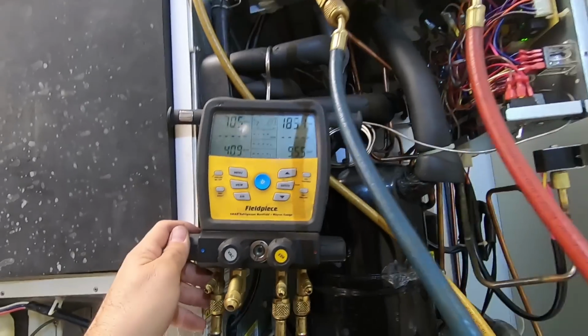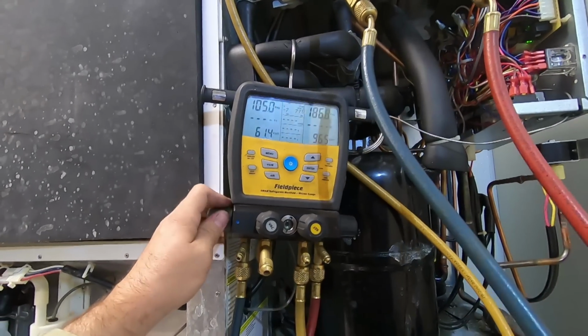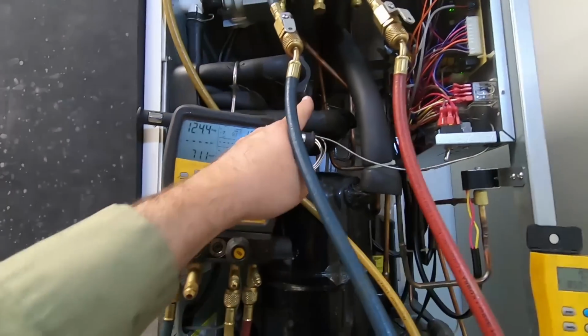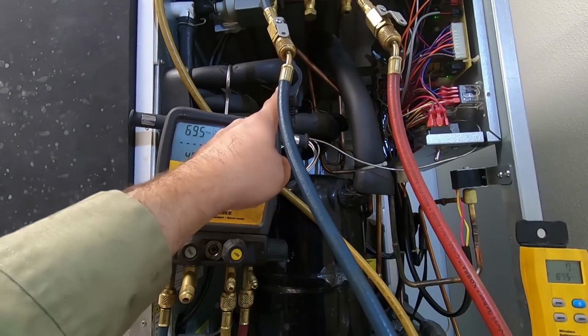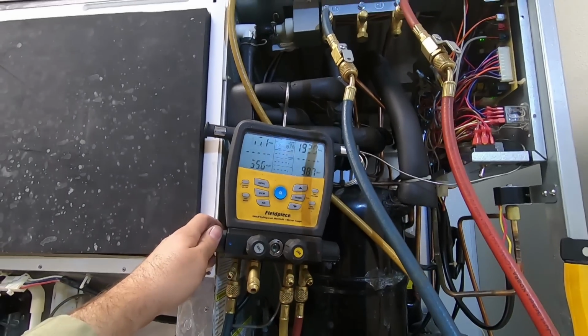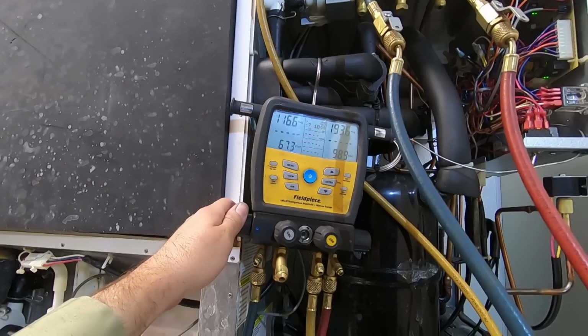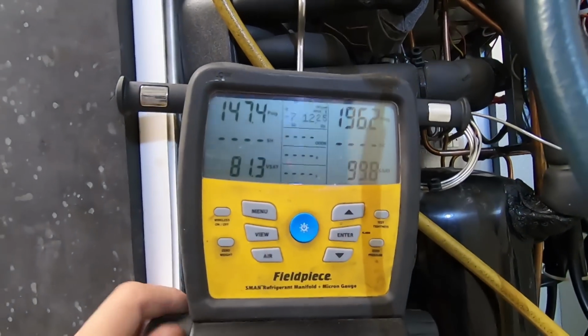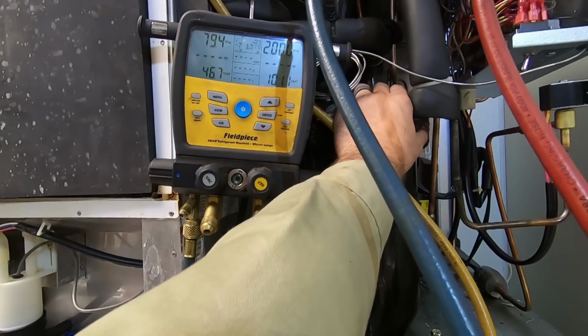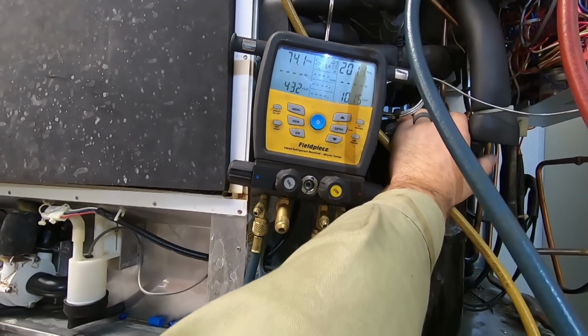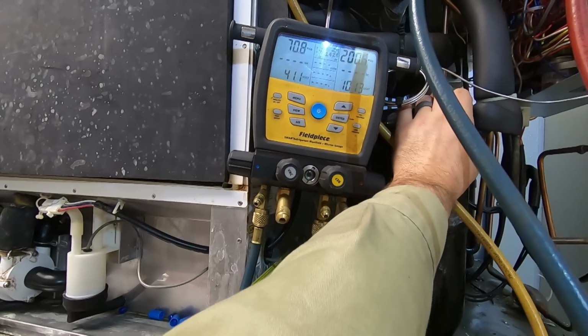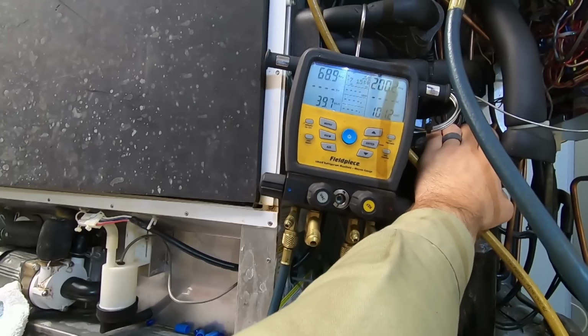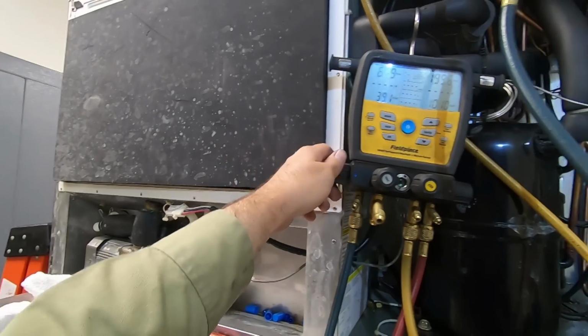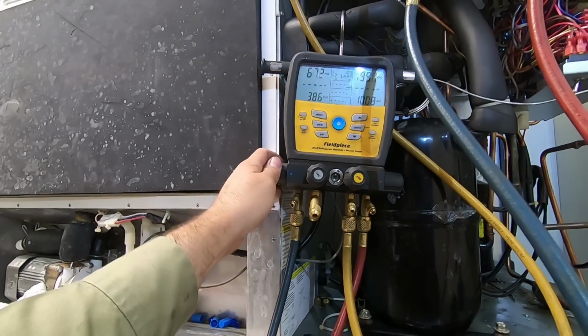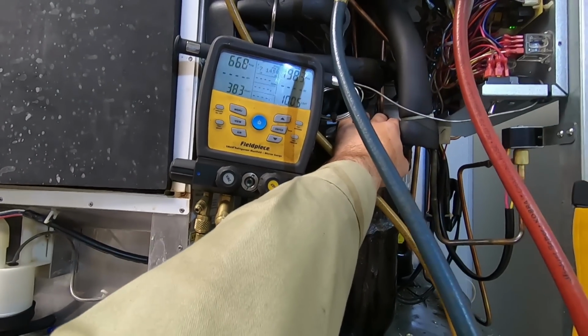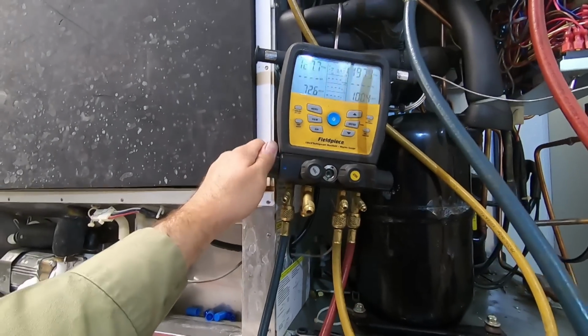So it's started in its harvest right now because the Hoshi's always starting to harvest. So I can put a little bit in there, you just got to be careful. I checked the hot gas valves. The lines coming off going through the check valves are both hot, so that means we're feeding through both check valves, so that's a plus. Be careful though charging it in a defrost, because it's just dumping refrigerant back to the compressor. I'd rather wait until it goes into a freeze mode and meters through the expansion valves. I could just do it slowly.